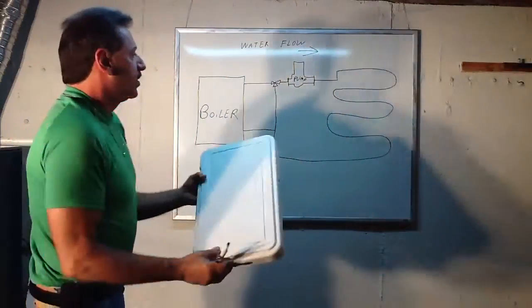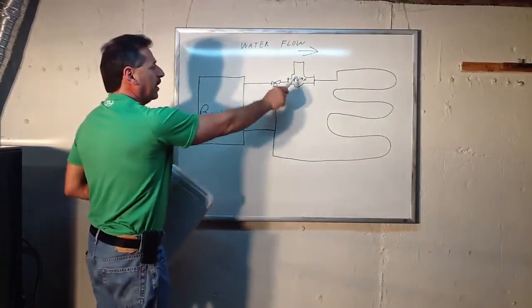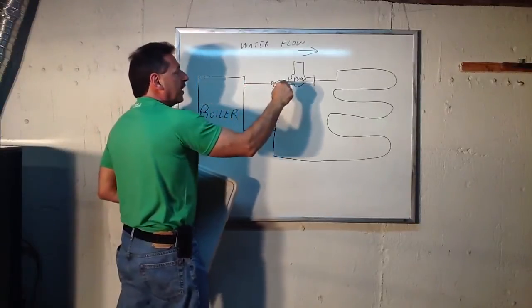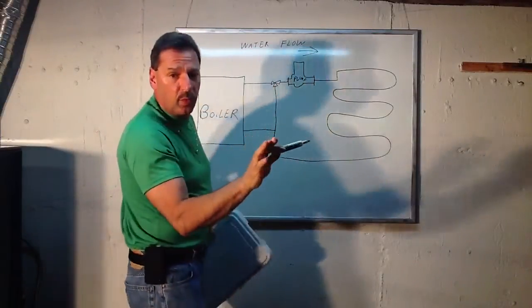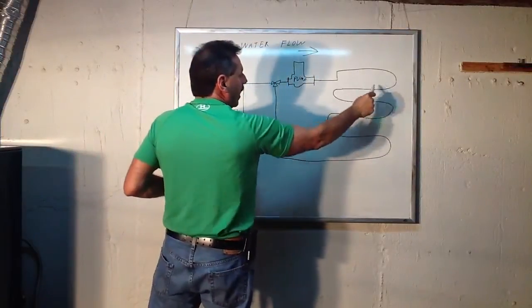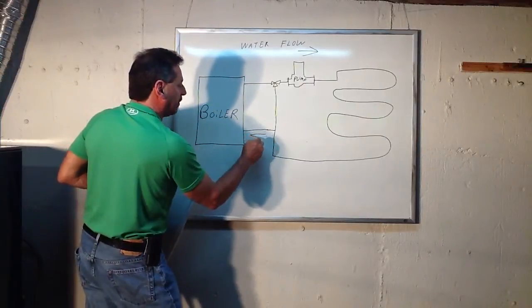So what takes place is the thermostat calls for heat and it turns on the circulator pump. As soon as the circulator pump goes on, it pulls hot water out of the boiler. Remember the water is 180 degrees. And it sends the water around the floor and then back into the boiler again. This is the return going back.